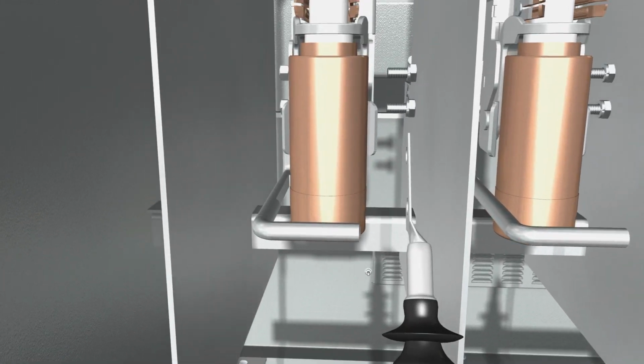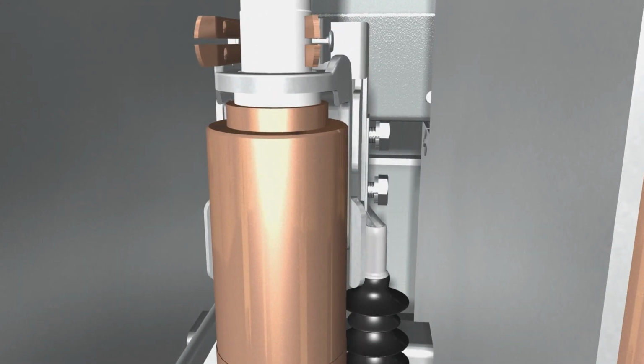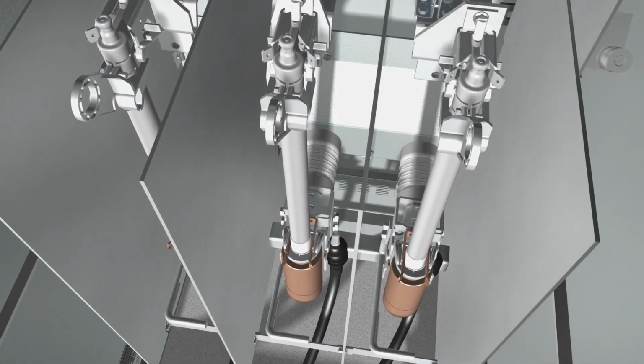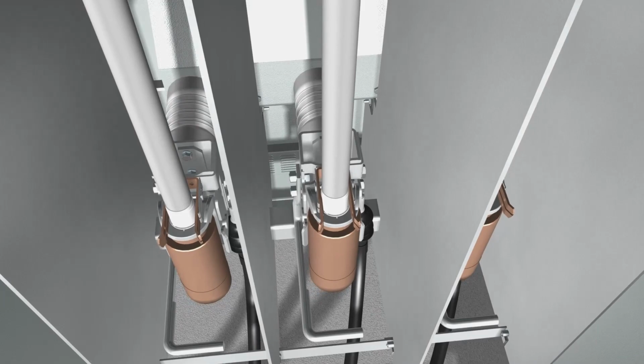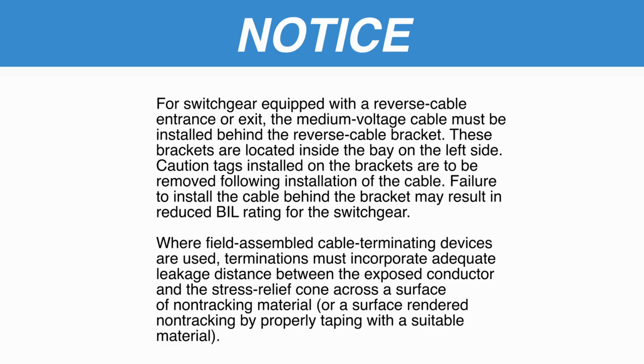Step 15. After all other connections have been completed and checked, make the medium voltage cable terminations, following the cable terminator manufacturer's instructions. Note: for switchgear equipped with a reverse cable entrance or exit, the medium voltage cable must be installed behind the reverse cable bracket. These brackets are located inside the bay on the left side. Caution tags installed on the brackets are to be removed following installation of the cable. Failure to install the cable behind the bracket may result in reduced BIL rating for the switchgear.